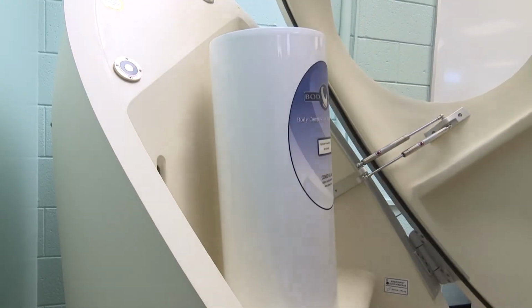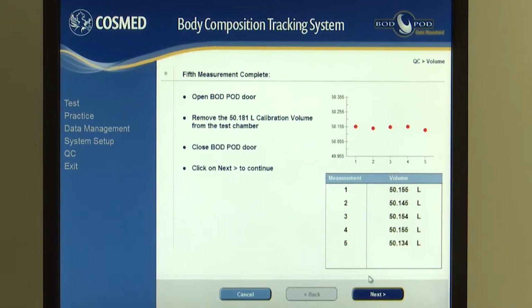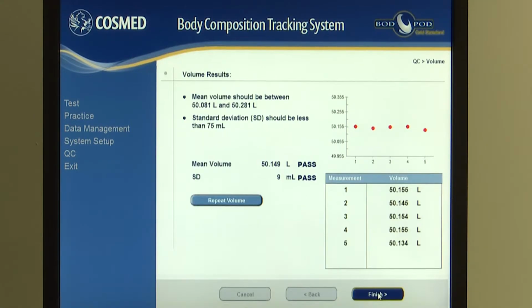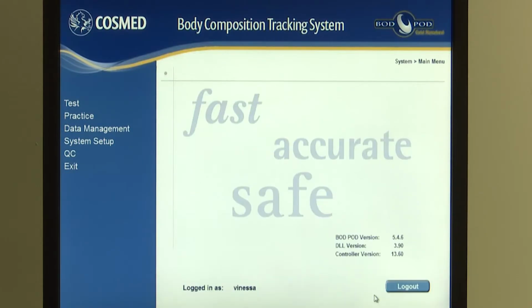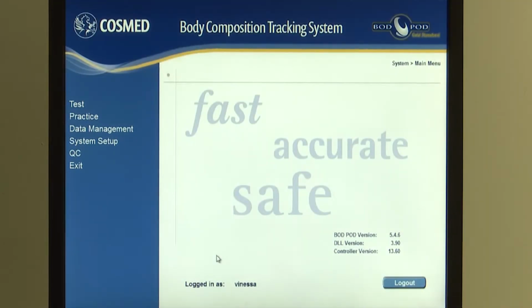Once the volume has been measured, the screen will indicate if the volume test was a pass or fail. If the test fails, it must be repeated. If it passes, go to the next step. The standard deviations are listed on the screen as well. Volume measurements are now complete, and the Bod Pod is ready for testing an individual's body composition.